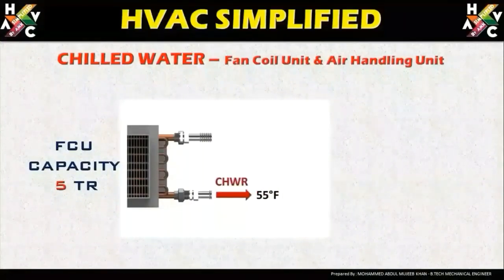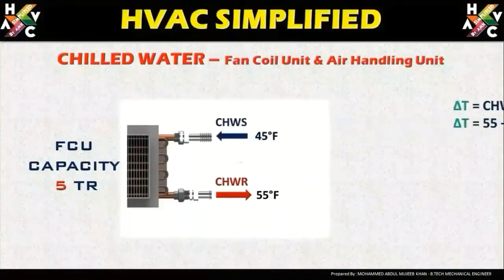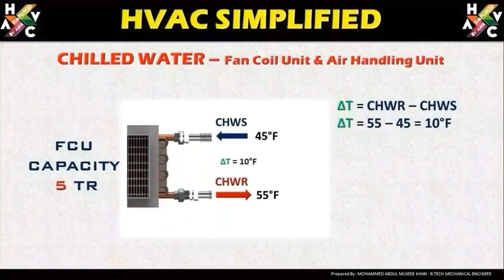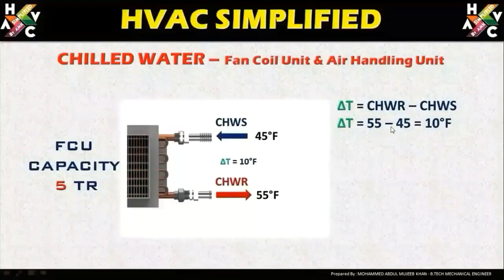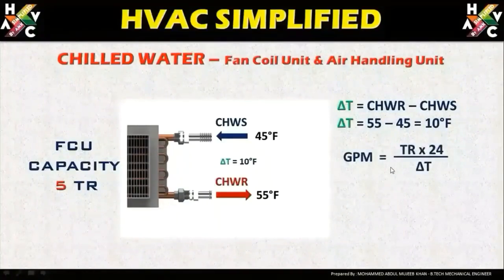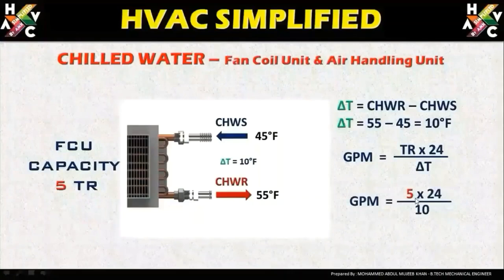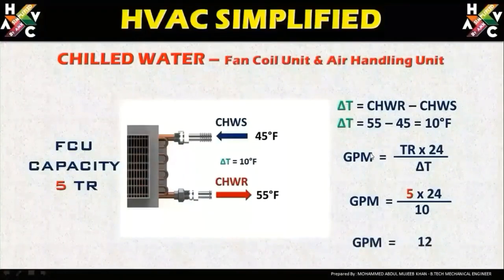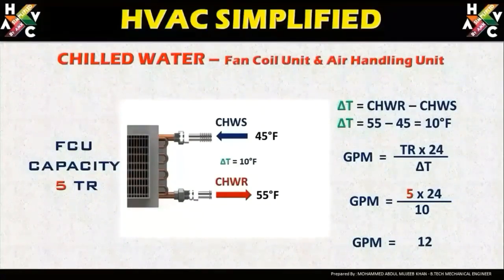Another criterion we need is the chilled water return and chilled water supply temperatures. Here we take the chilled water return as 55°F and the chilled water supply as 45°F. So delta T = 55 − 45 = 10°F. Using the formula GPM = TR × 24 / ΔT, we get 5 × 24 / 10, which equals 12 GPM. So the required GPM for this fan coil unit is 12, and this is how you derive GPM for any fan coil unit or air handling unit.